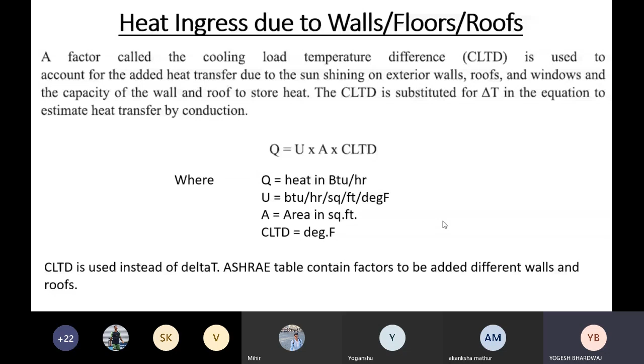So actual delta T is your design ambient condition, which is peak ambient condition, and design indoor condition. So the delta T for ambient condition and your room design condition is your actual delta T. Then you have to add 10 degree, 20 degree, 30 degree, depending upon ASHRAE guidelines. So like in case of roof, we add 25 degree directly into the delta T in Fahrenheit.